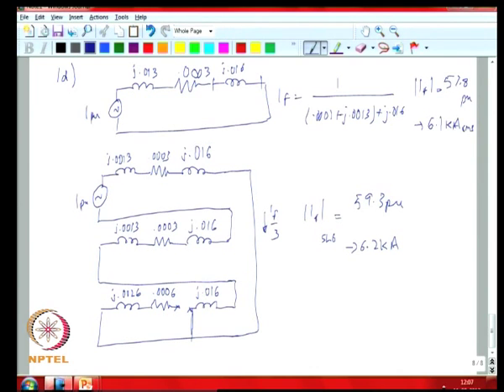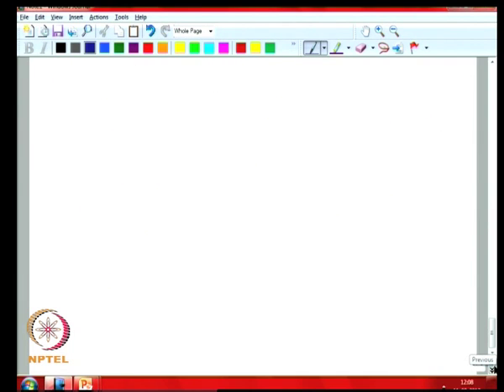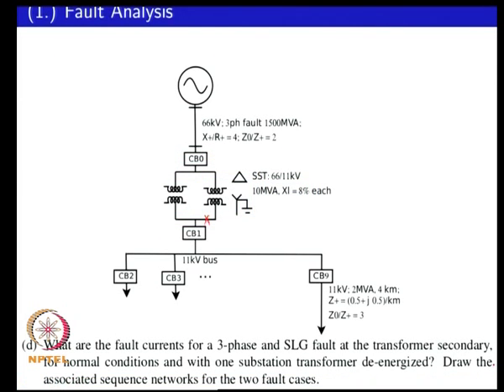You can see that the fault current level for the single line-to-ground fault case is higher than the three-phase fault case. Essentially the reason is that the 66 kV side impedance is bypassed because of your delta-y transformer configuration. You could then look at the next case where you have both transformers present — I will just write the result and put it in a table.